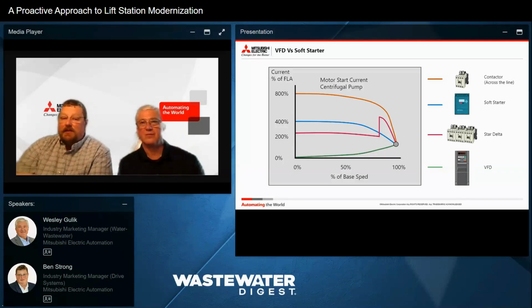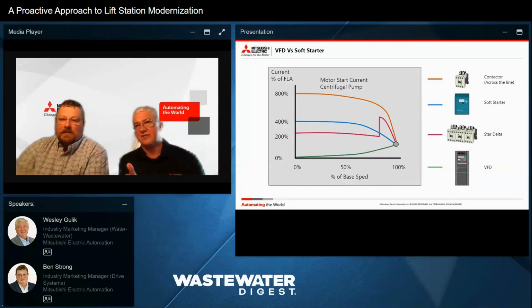And the reason for that is you can control the ramp up. You don't have this huge change in pressure that translates into shock waves, that translates into slamming check valves, or these huge transients that can damage some of these systems. Like we said, if your piping system's 40 years old, maybe you don't want to be shocking them every time your pump starts. So these are things to consider about what technologies you put into your lift stations. It's a very, very good point. So, I mean, as you can see, from the simple, on off, very easy to control, but very simple, results to the variable frequency drive.